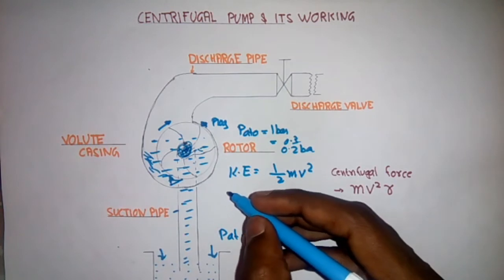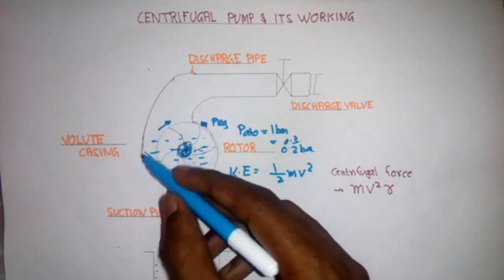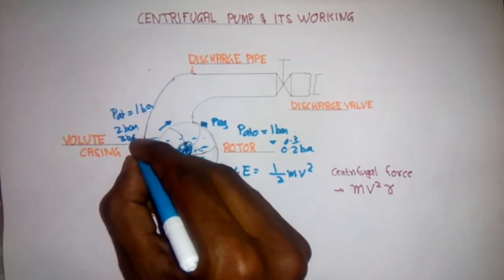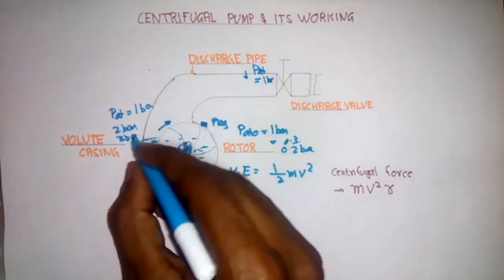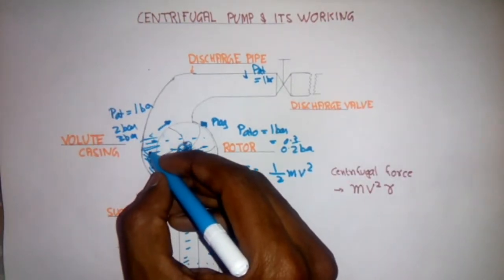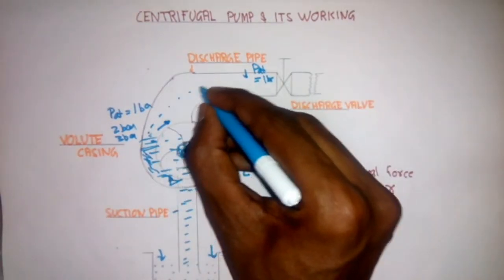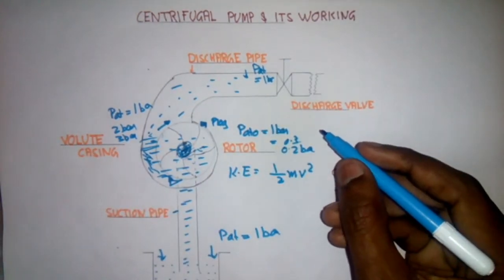Now the volute casing comes into action. What it will do? It will reduce the velocity of the liquid and increase its pressure. The volute casing increases its pressure. Before, the pressure is atmospheric pressure that is 1 bar. And now it is increasing to 2 bar, 3 bar. And here at the discharge side the pressure is atmospheric pressure that is 1 bar. Now the pressure increased by the volute casing is more than the pressure at the discharge side. So the water starts moving towards the discharge. This is the working of centrifugal pump.